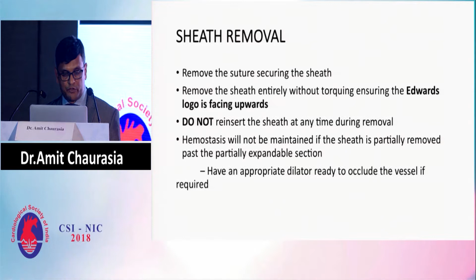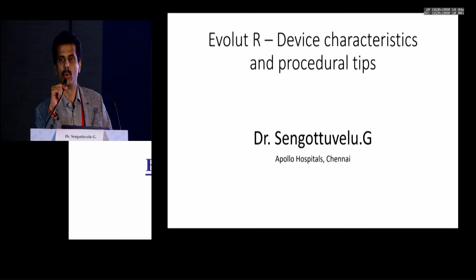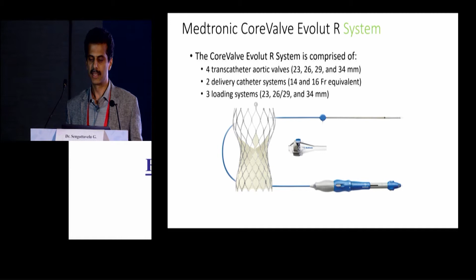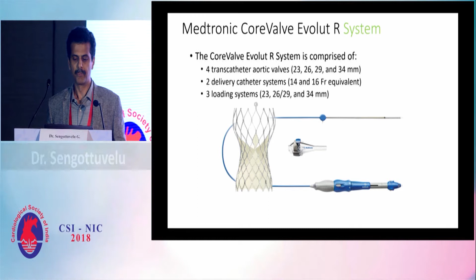Thank you very much. So Evolut R was one of the valves from Medtronic which was available to us quite early in India. They started with the CoreValve initially, and then quickly we had the Evolut R valve. And our TAVI program in India is now mostly done with the Medtronic Evolut R valve. As you know, Evolut R valve comes in 4 sizes, 23, 26, 29, and now 34. Recently, Evolut Pro has also been introduced, but it's still not approved in India. So there are 2 delivery systems, a 14 and a 16 French equivalent, and 3 loading systems depending on the valve size. So it's got a self-expanding frame.